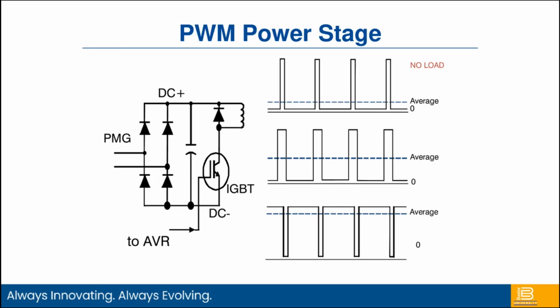At no load, you can see I have these little bitty pulses. If I'm at average load, I've got a little bit bigger pulse. That's this middle line here. And if I'm at full forcing, or I need a lot of DC into my field, I'm going to have a full gate, basically gating as much as I possibly can to provide excitation to the field.